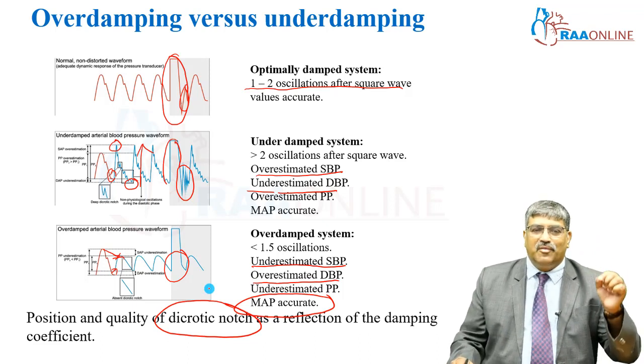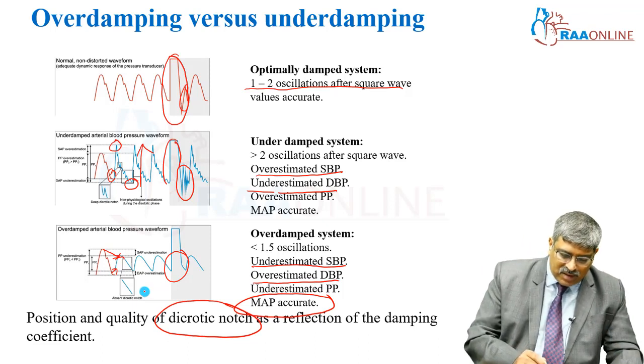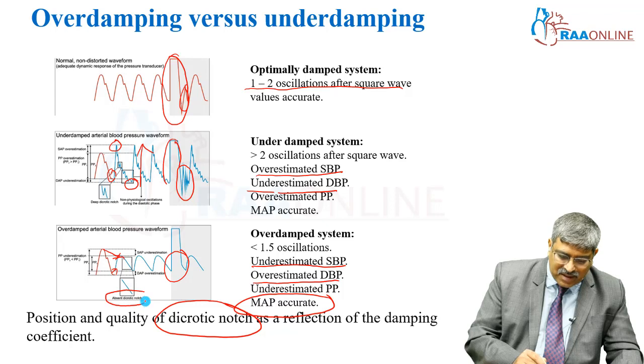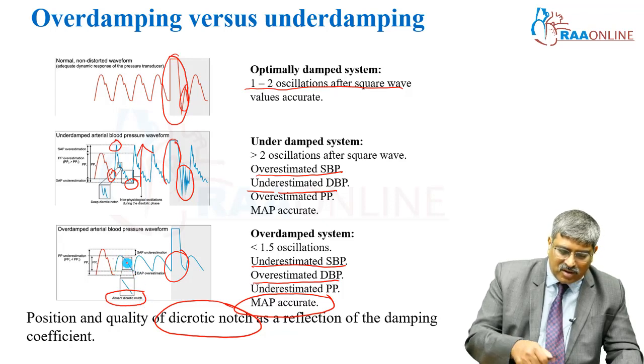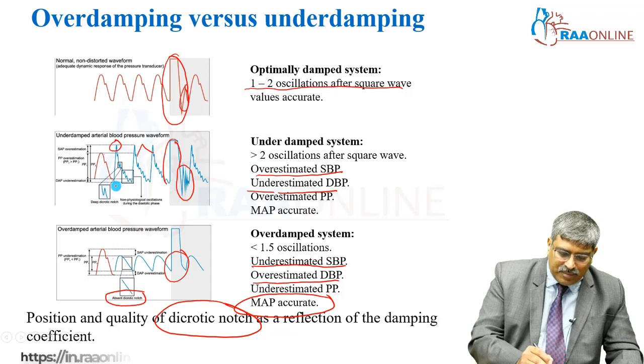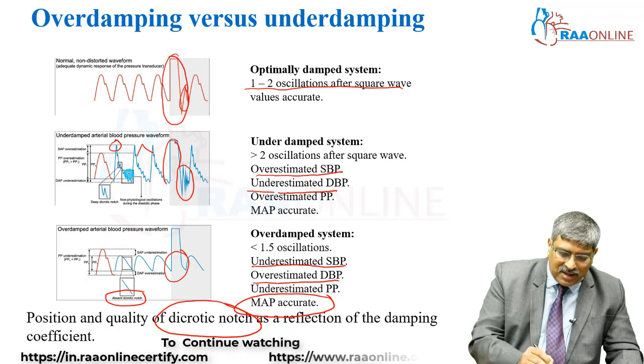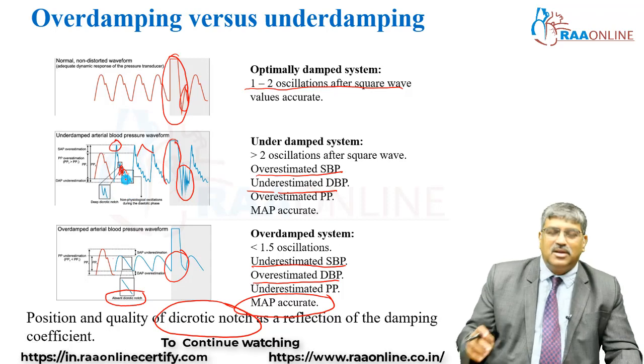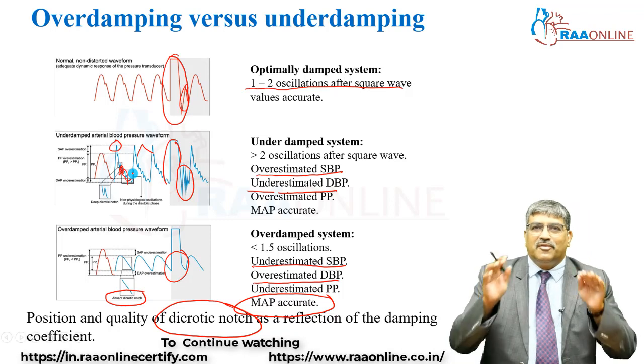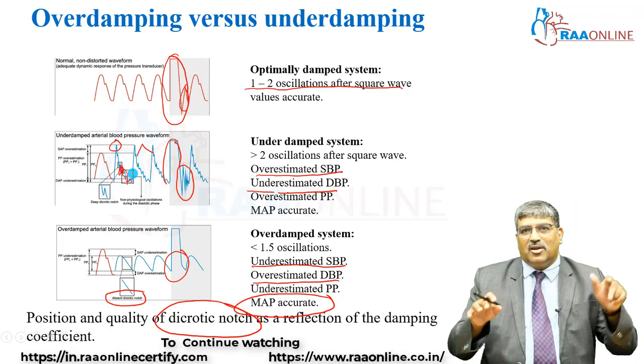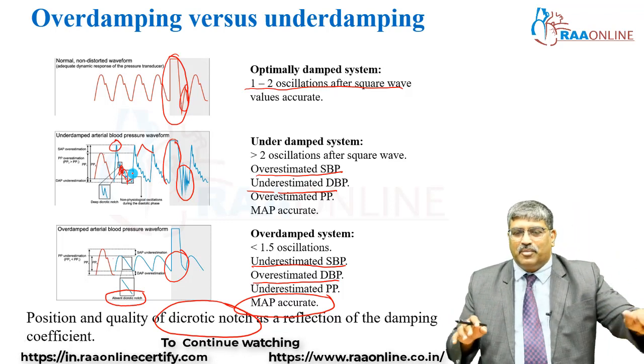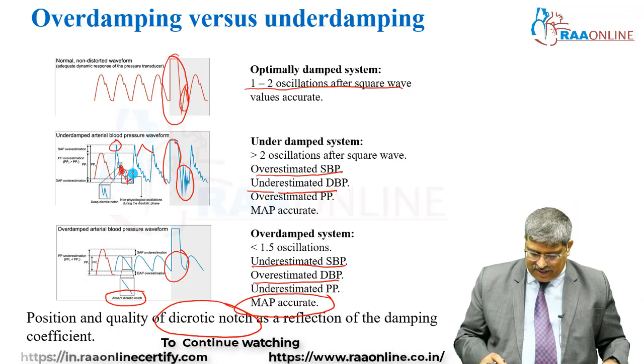You can also identify under-damping and over-damping using the dicrotic notch. In over-damping, there is an absent dicrotic notch — here you can see no dicrotic notch. In under-damping, you can see a deep dicrotic notch. So with the dicrotic notch, you can determine whether the system is under-damped or over-damped.